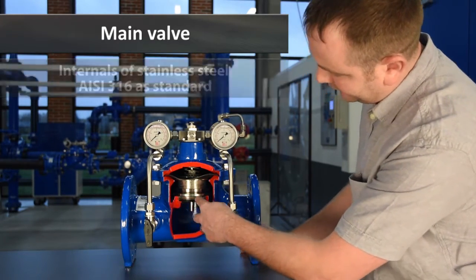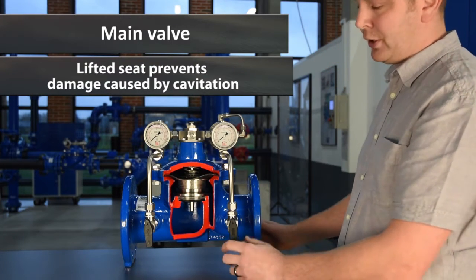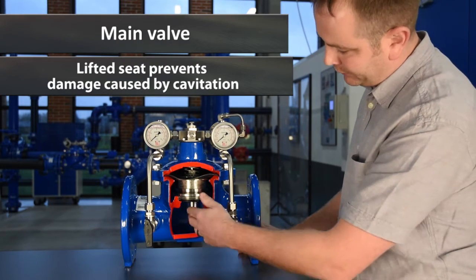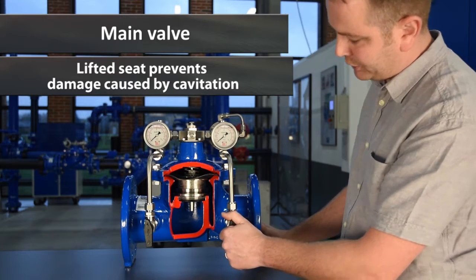Inside the main valve we have the lifted seat. The lifted seat offers a high KV value when the valve is fully open, and of course with the lifted seat you have reduced cavitation.